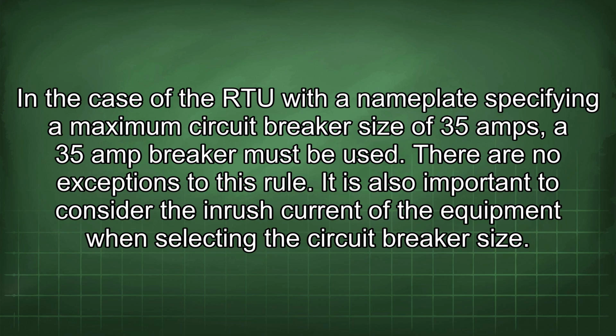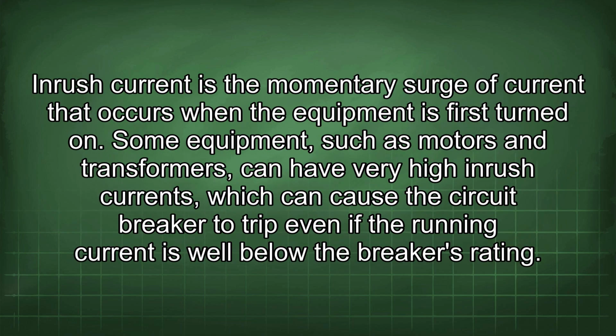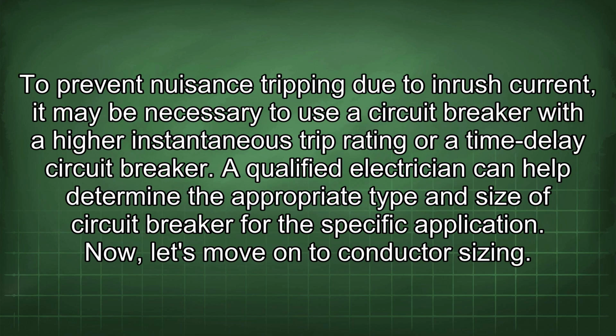It is also important to consider the inrush current of the equipment when selecting the circuit breaker size. Inrush current is the momentary surge of current that occurs when the equipment is first turned on. Some equipment, such as motors and transformers, can have very high inrush currents, which can cause the circuit breaker to trip even if the running current is well below the breaker's rating. To prevent nuisance tripping due to inrush current, it may be necessary to use a circuit breaker with a higher instantaneous trip rating or a time delay circuit breaker. A qualified electrician can help determine the appropriate type and size of circuit breaker for the specific application.